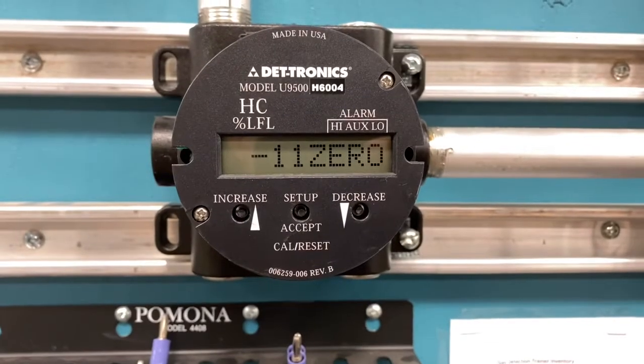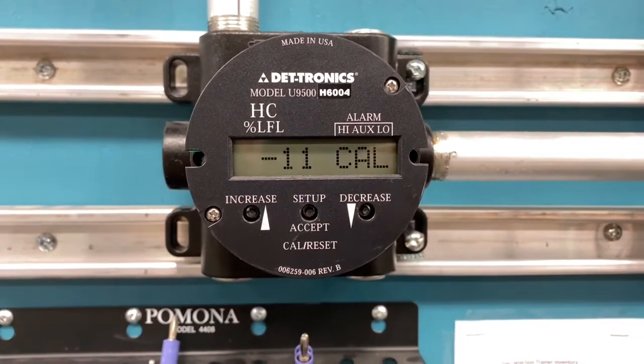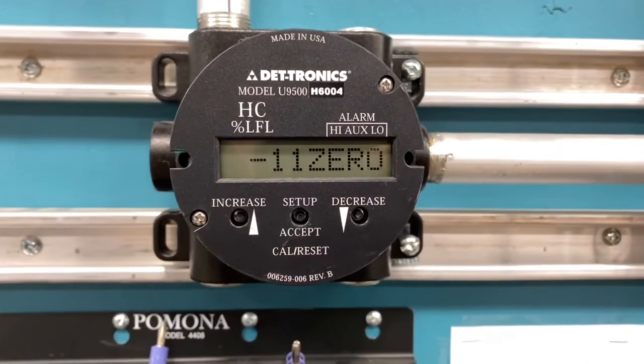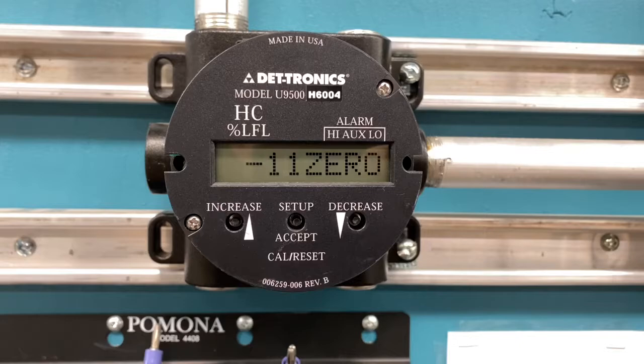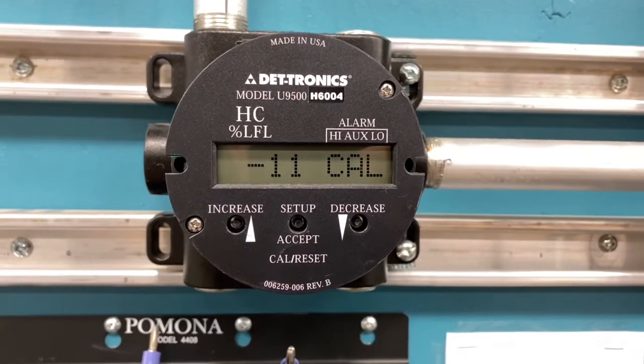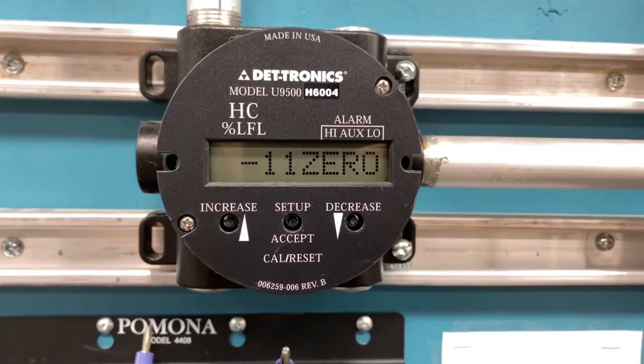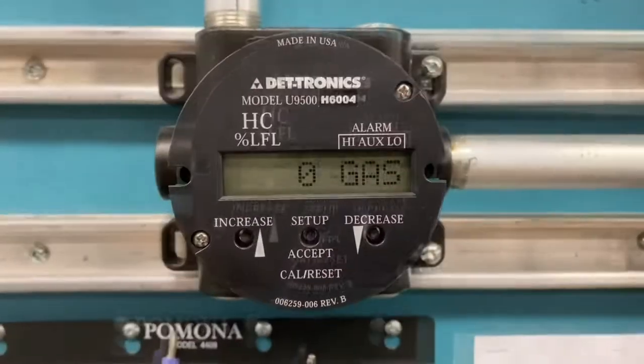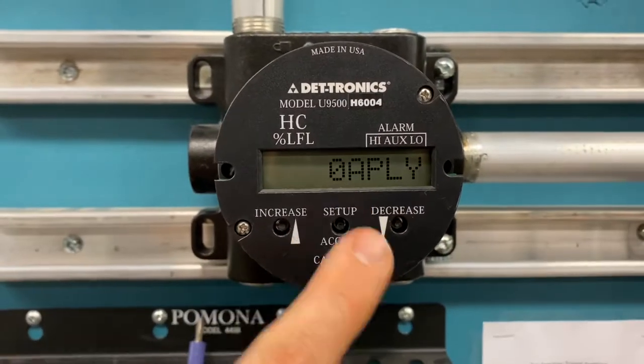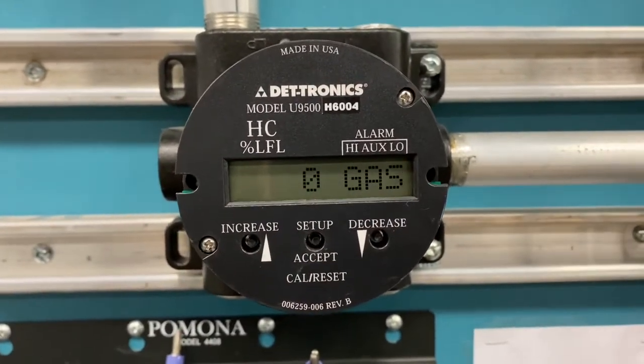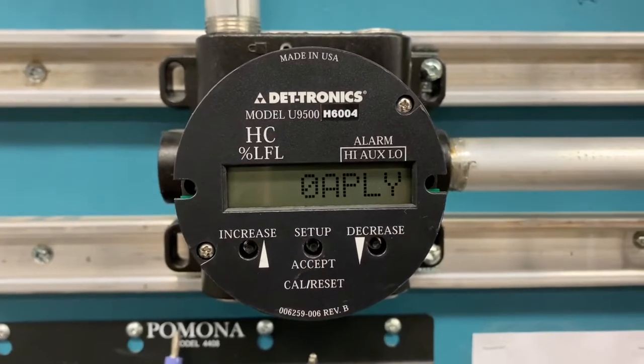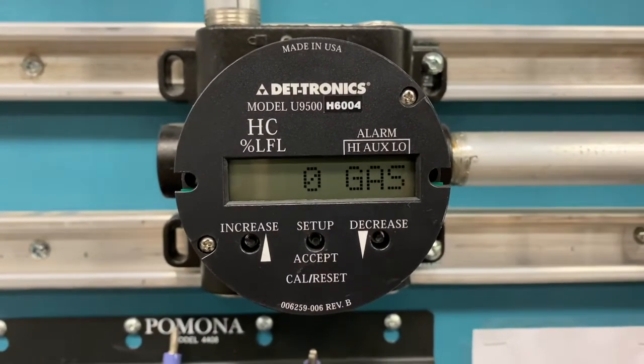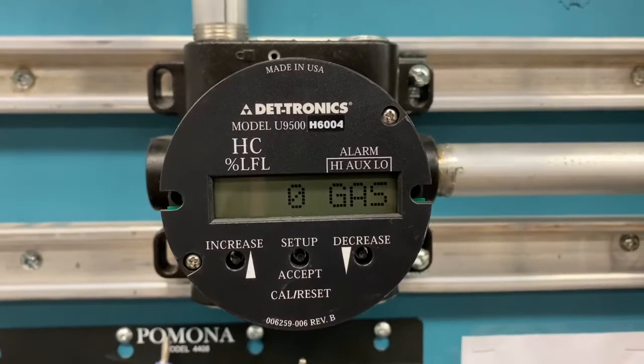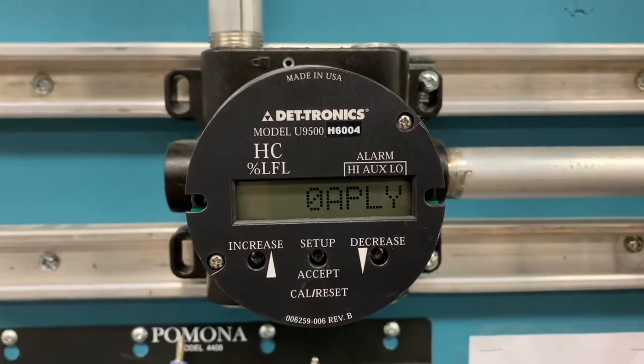There, it's doing a 0 cal right now. Once it's done the 0 cal, it's going to ask us to apply gas. But since we're not doing the calibration, we're not going to bother with applying the gas. After we've applied our zero gas for a little bit, now it's saying apply gas. This is when we would apply our 50% LEL, and then it would calibrate to that. But since it doesn't need to be calibrated, I'm just going to power it down because I don't want to use up any of my calibration.